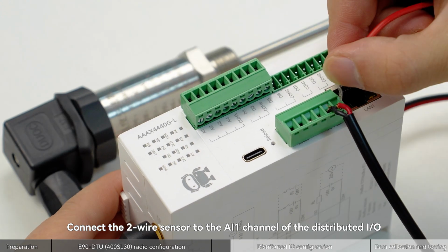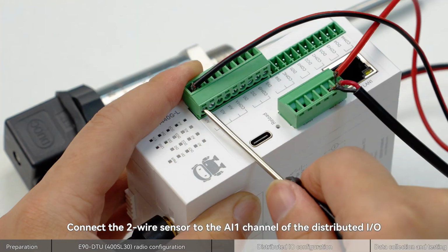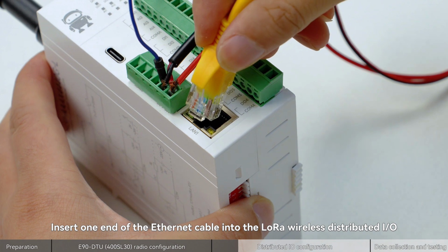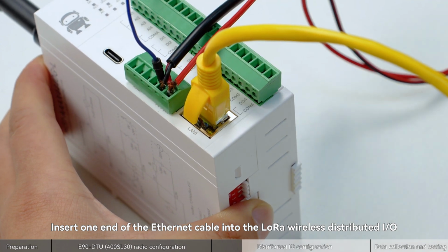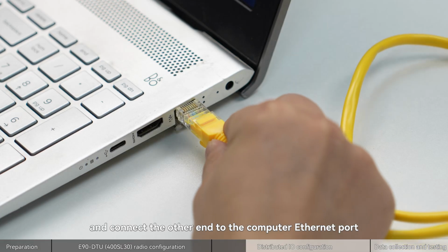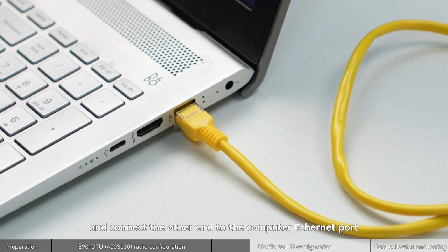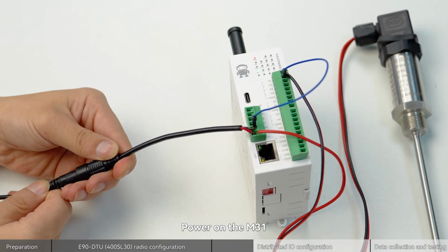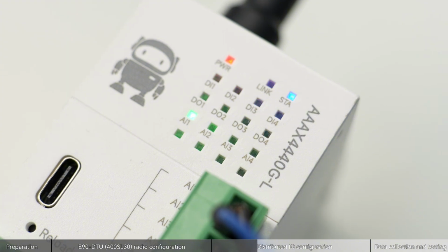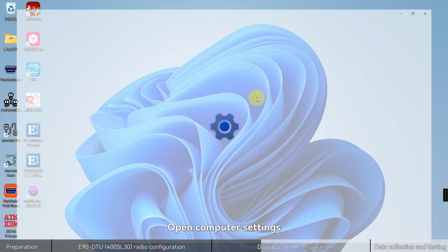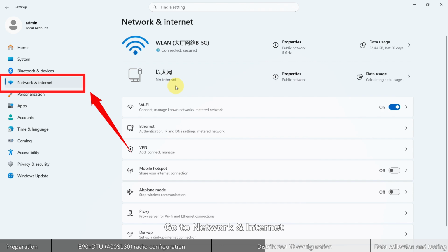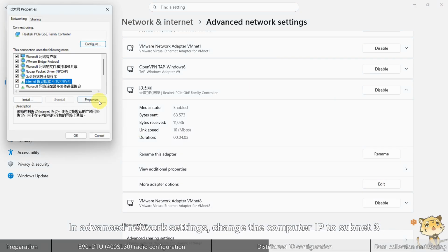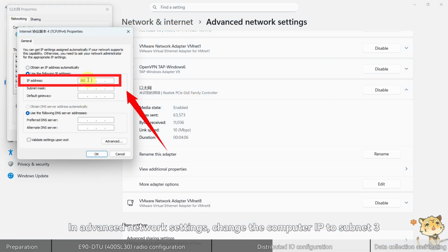Connect the 2-wire sensor to the AI1 channel of the distributed I/O. Insert one end of the Ethernet cable into the LoRa wireless distributed I/O and connect the other end to the computer Ethernet port. Power on the M31. Open Computer Settings. Go to Network and Internet. In Advanced Network Settings, change the computer IP to subnet 3.